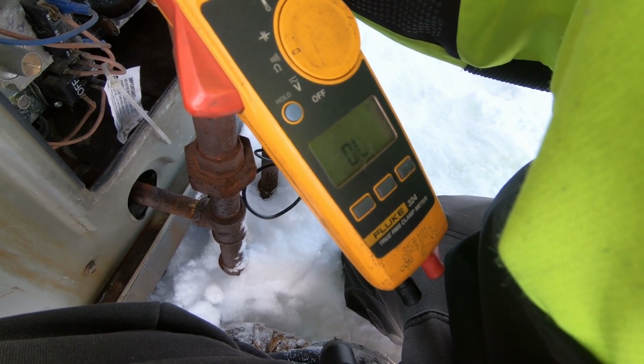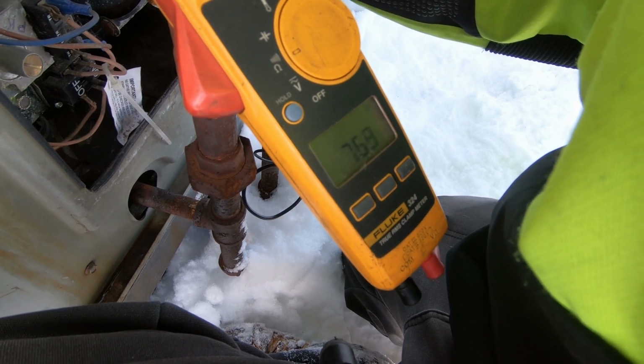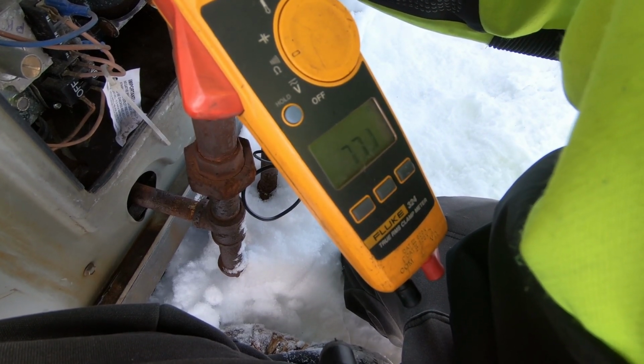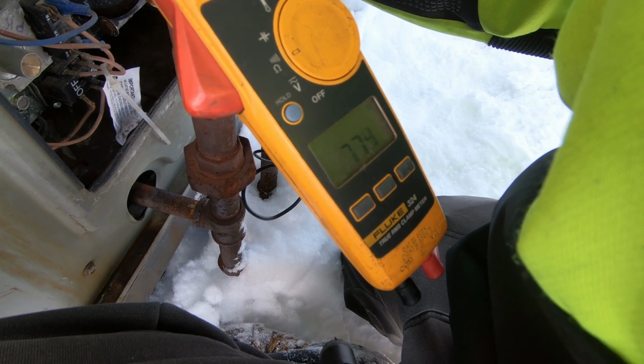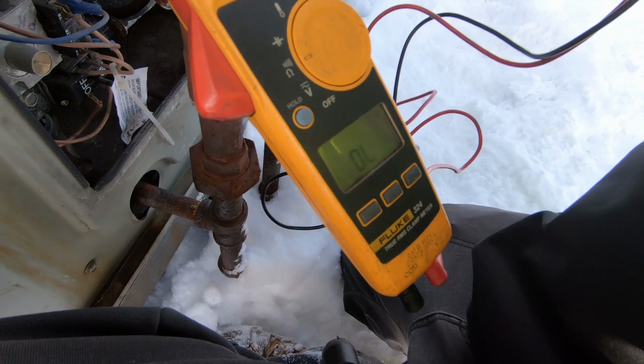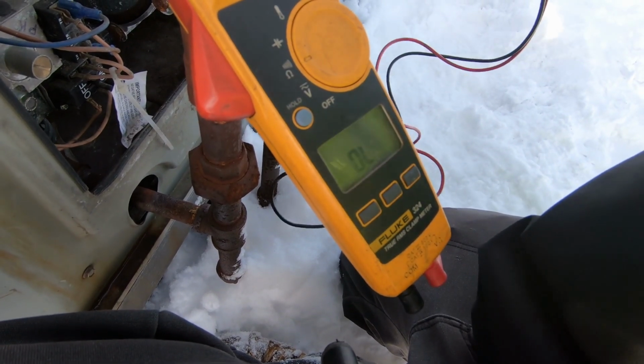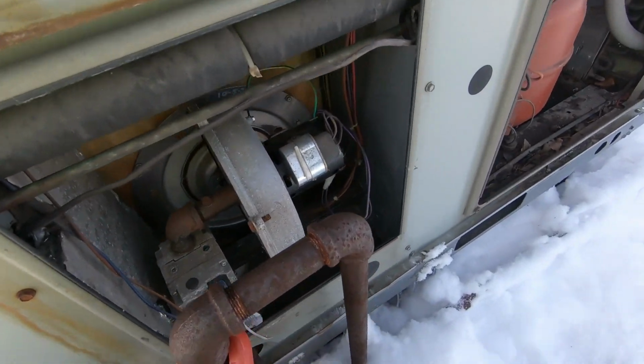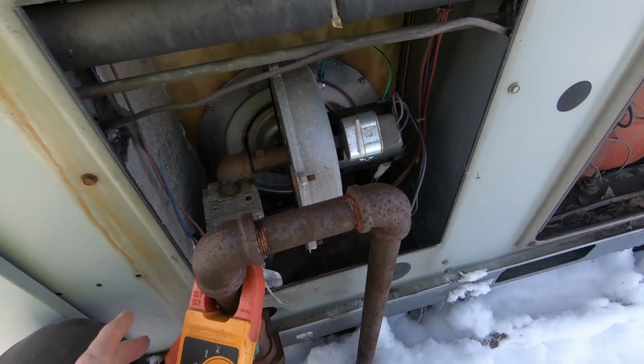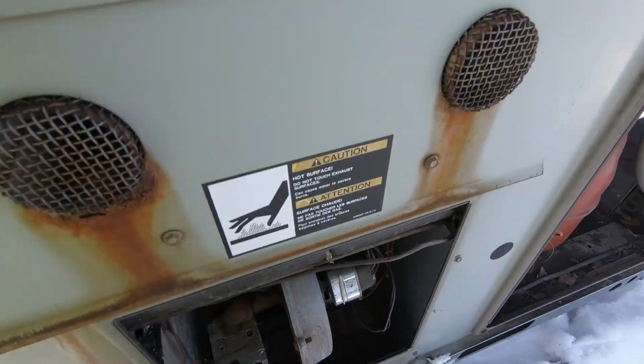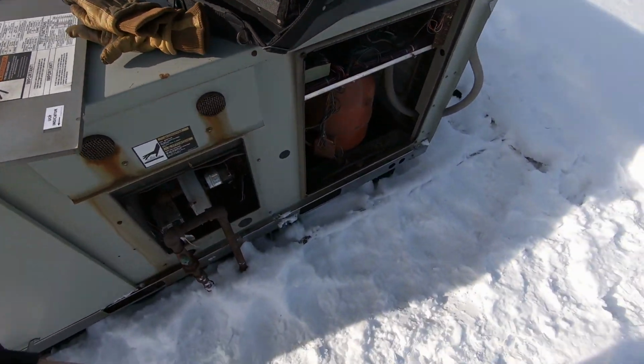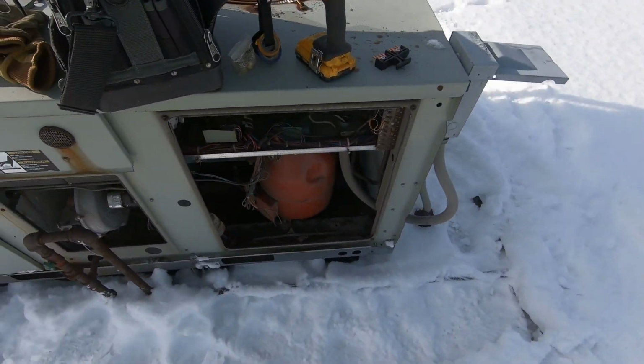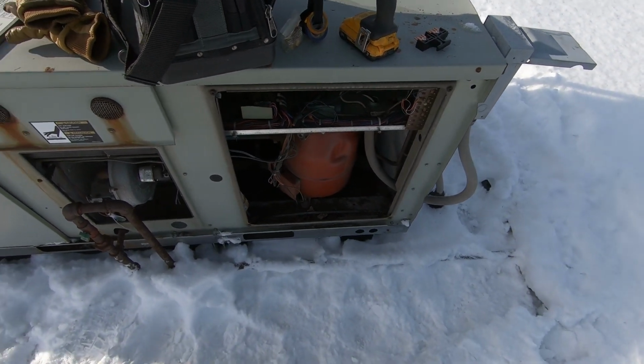Come on. All right, showing 760, 770, 772. Anyway, it should be under 100. So right off the bat, bad igniter. Combustion blower sounds terrible. Gas valve works, blower motor works, heat exchanger's in good shape. Electrical looks all right. I'm gonna go ahead and cut W and reapply power.